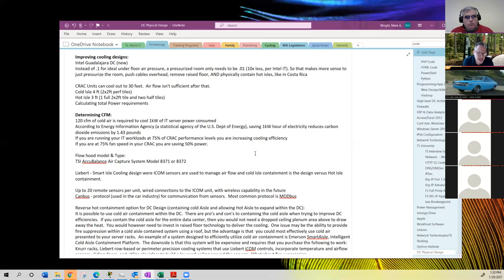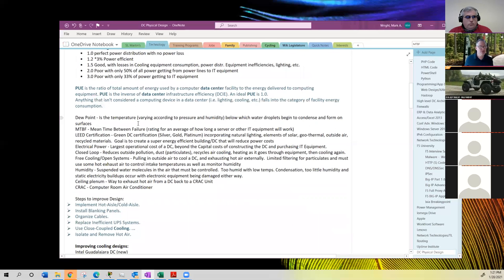Then they had IBM analyze and test, cut these things open, break them down, and see if the mean time between failure - MTBF - had been reduced in any way. Mean time between failure means the average time a server or other IT equipment will work, the time between failures. So a server, and all its components, has a mean time between failure for a hard drive, a network interface card, a processor, a stick of RAM memory - and those all have failure rates, or mean time between failure, measured in hours.